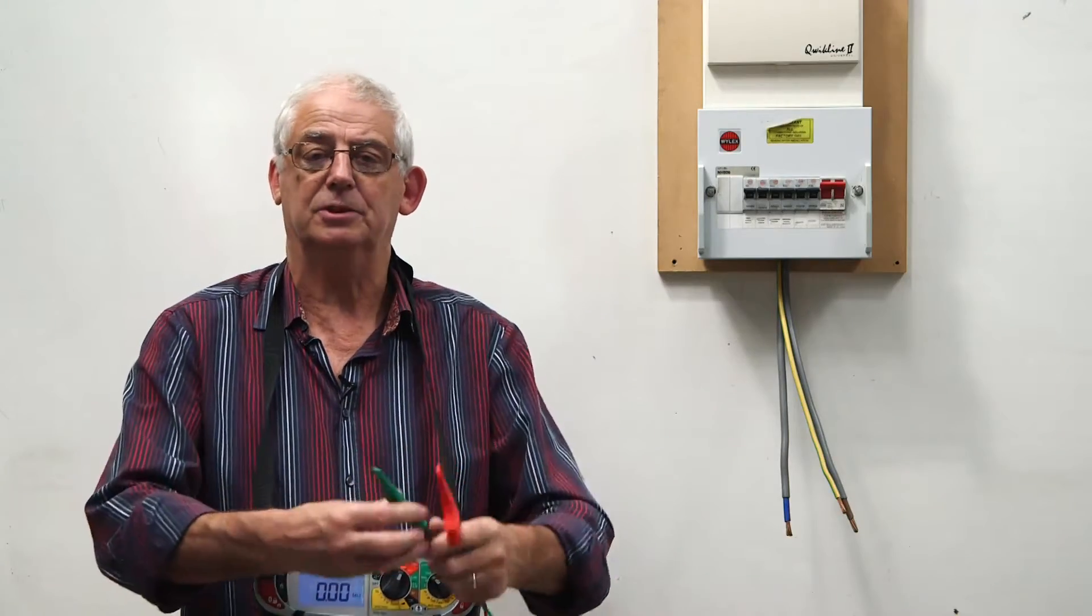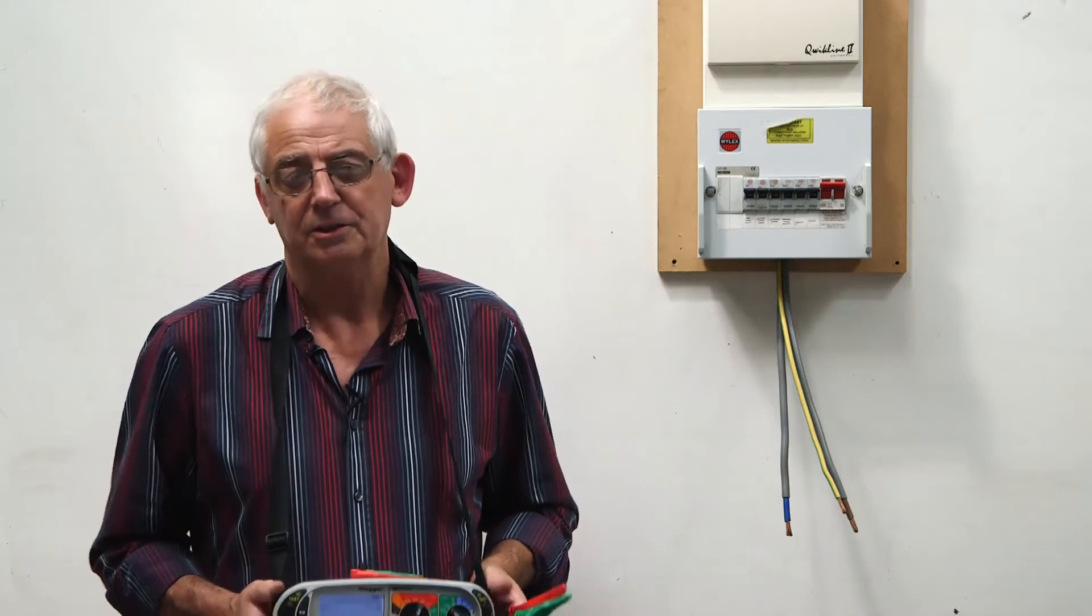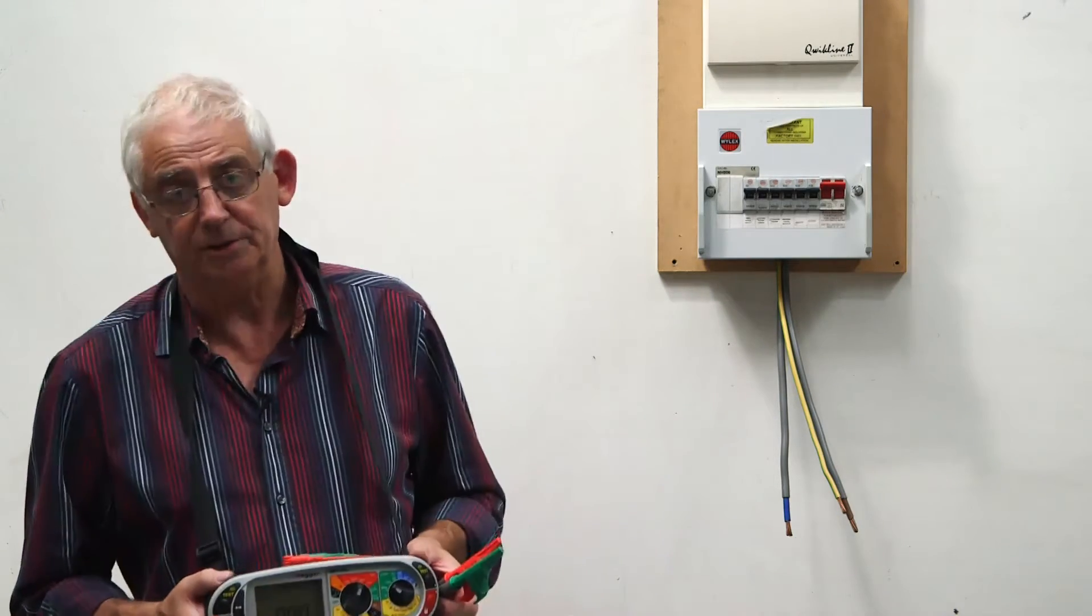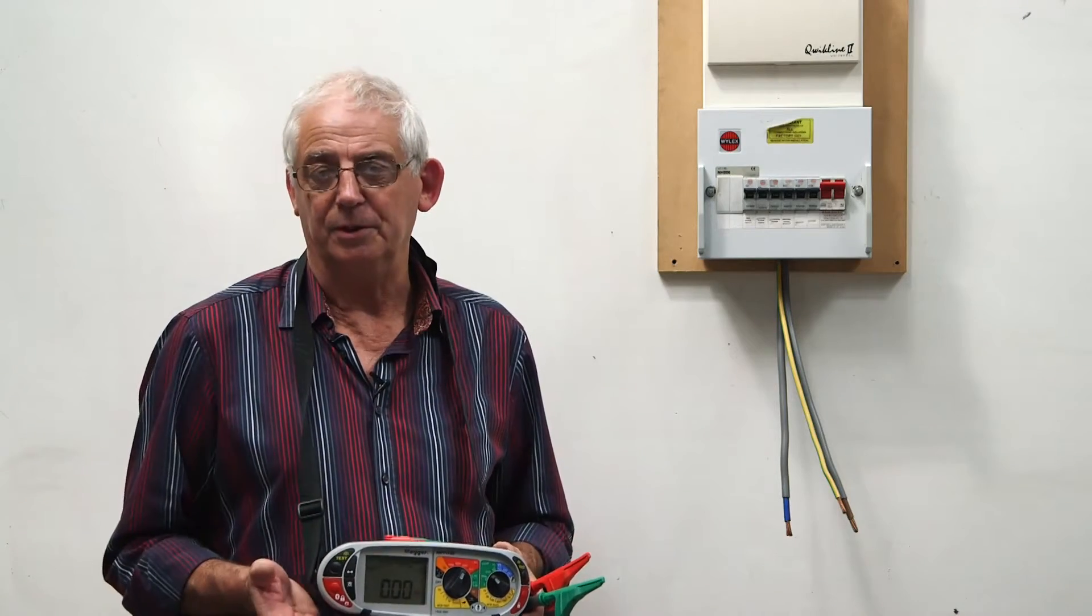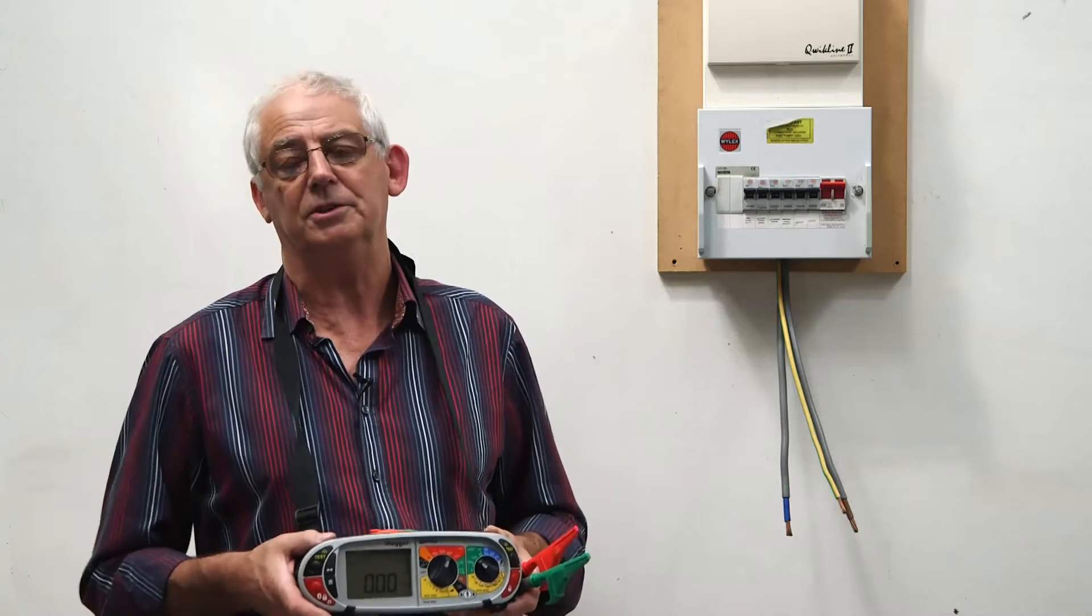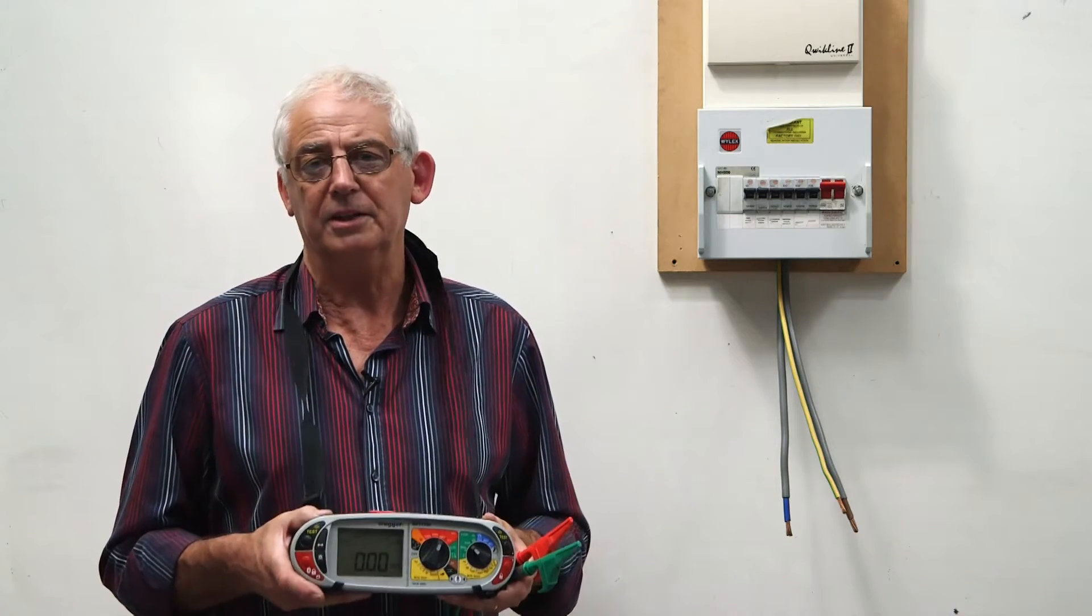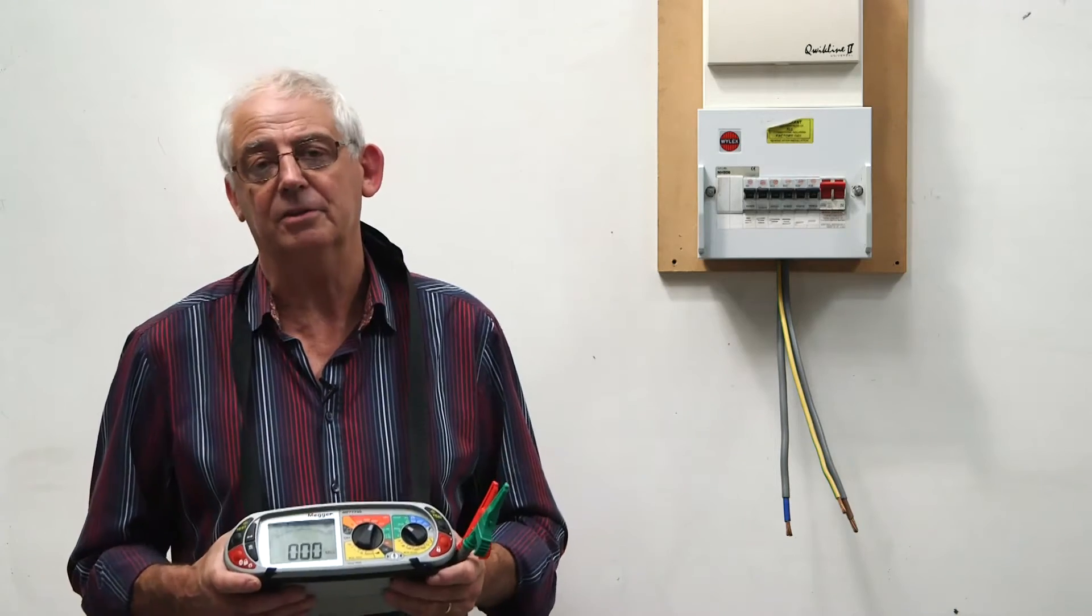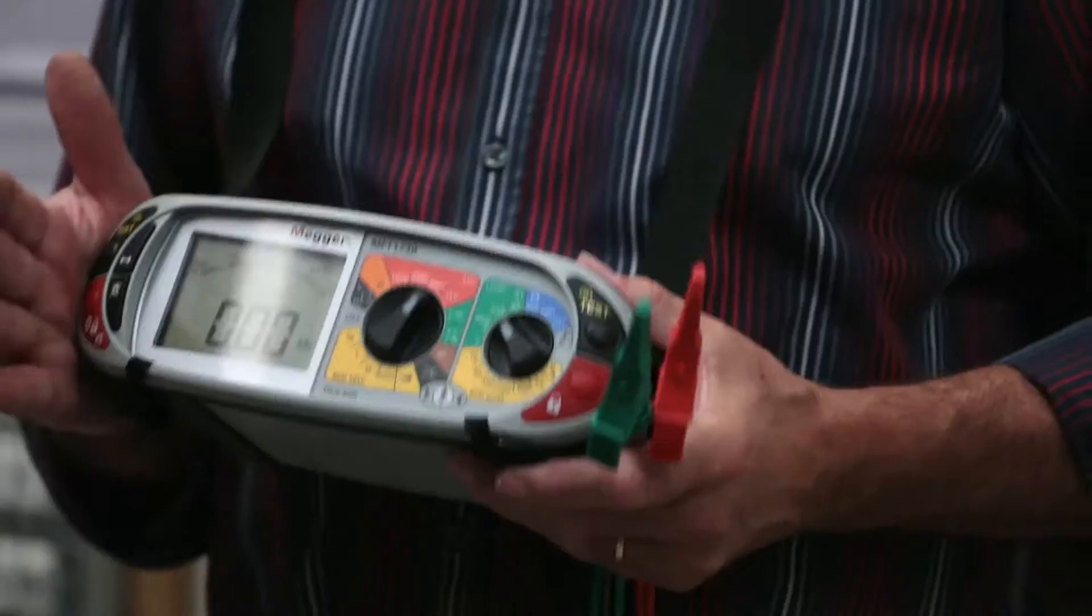I also need to make sure the instrument is accurate. Some people say they need to make sure it's calibrated. That's not strictly true. It needs to be calibrated when you buy it, but you need to maintain a record of its accuracy throughout its life. Providing it's accurate, it's okay. This is my test instrument and I know it's accurate, so I'm quite happy to use this.